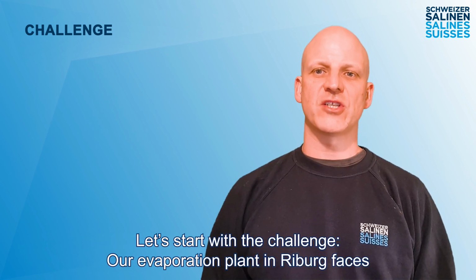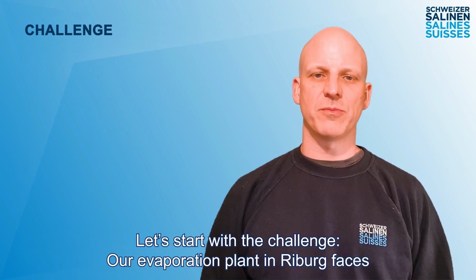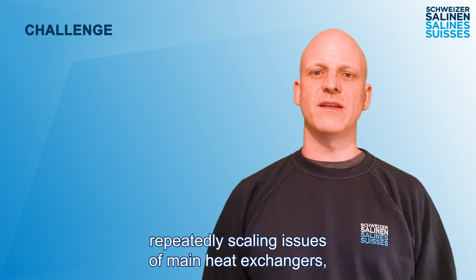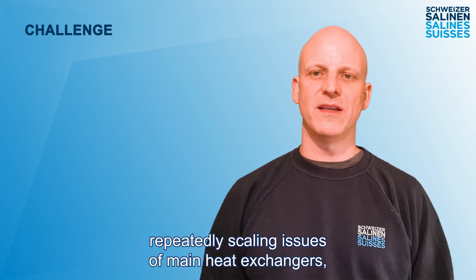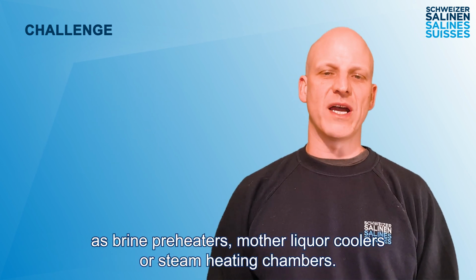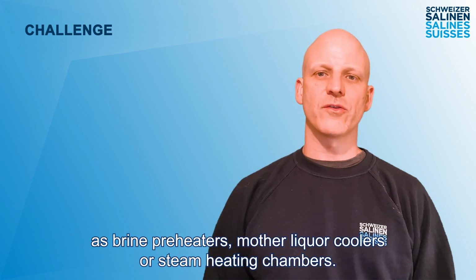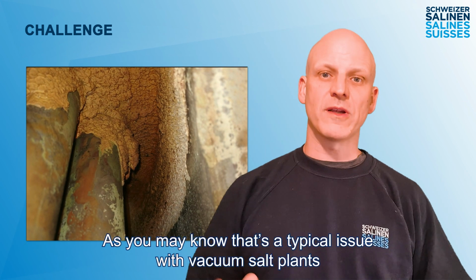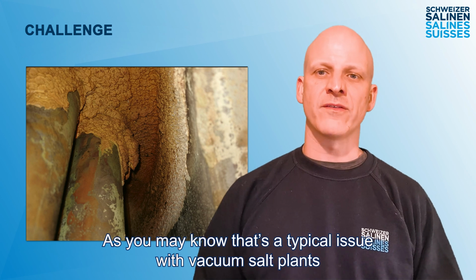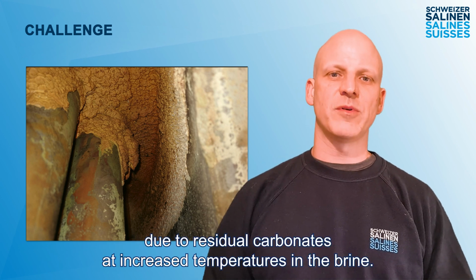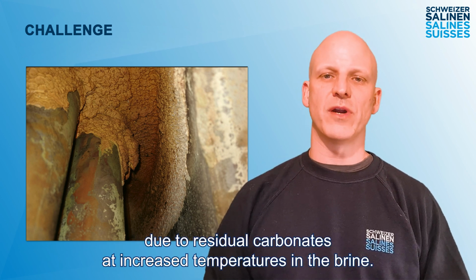Let's start with the challenge. Our evaporation plant faces repeatedly scaling issues of main heat exchangers, such as brine preheaters, mother liquor coolers, or steam heating chambers. As you may know, that's a typical issue with vacuum salt plants due to residual carbonates at increased temperatures in the brine.